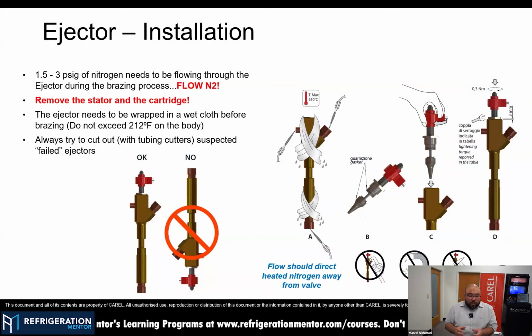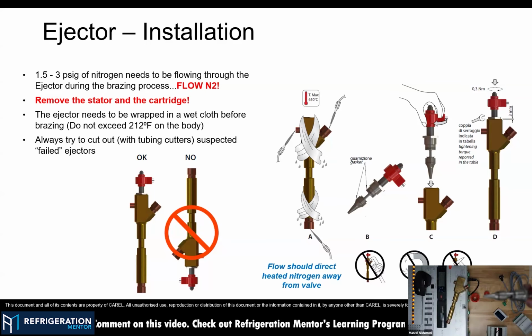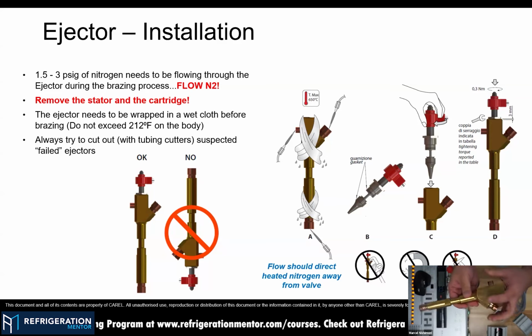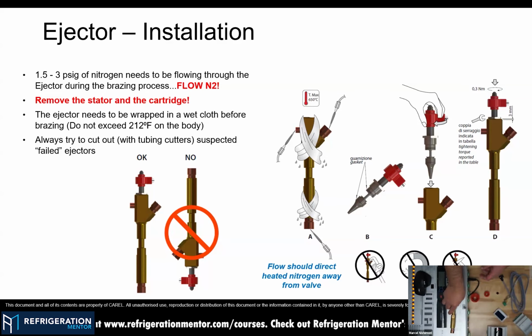So what precautions do you need to have? When you are welding the valve, first thing, you need to weld it with a wet rag here, to cool down the internal components. The same principle as a solenoid valve, an electronic expansion valve, or even a thermostat. This is to avoid heat propagating inside the components and damaging them. Another main point is that ejectors are serviceable, so you can remove the cartridge and install the ejector without the cartridge, so you don't deform or damage the O-rings inside it. We strongly recommend it, it's mandatory to remove it. So you can just use the wet rag here and then make your welds as in a traditional system.